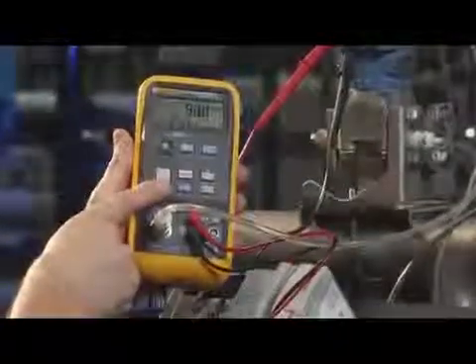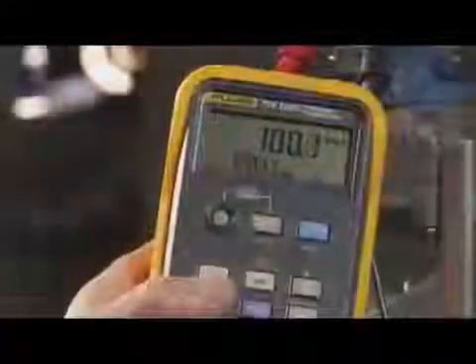Next, close the vent valve. The next test point, 50%, is 100 inches of water. We'll use the electric pump to generate 100 inches of pressure. Once the 719 gets close, you can use the vernier to adjust exactly 100 inches of water and verify for 12 milliamps.